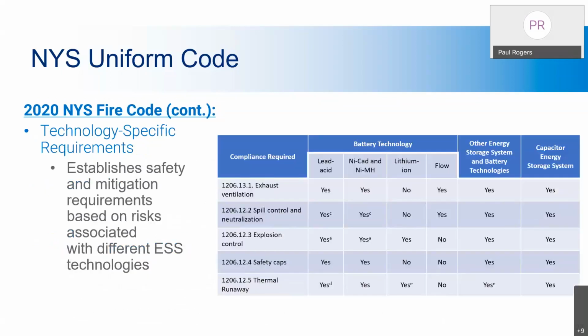I'm always big on these matrices. I think they do a good job telling you where to go and what you need to do. You'll see a lot of that in the New York State Fire Code and in NFPA 855. But one thing I really want you to focus on is the section on other energy storage and battery technologies. There's clear prescriptive criteria for lead acid, nickel cadmium, nickel hydride, lithium ion, or flow type batteries, but when it comes to other types, a lot of people don't know what they'll have to do - even the fire department doesn't know exactly.